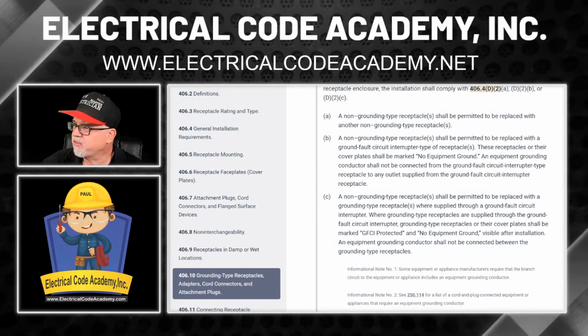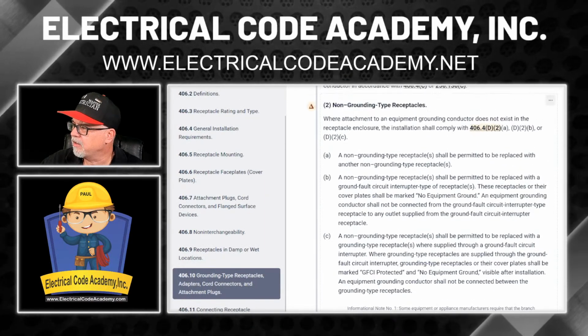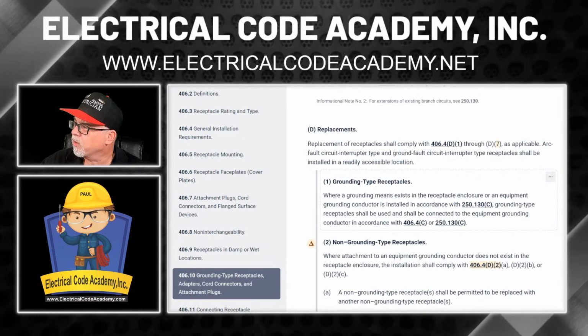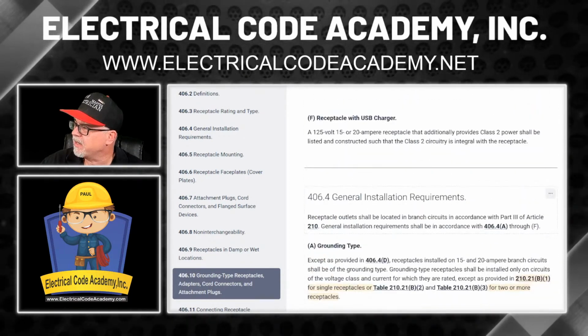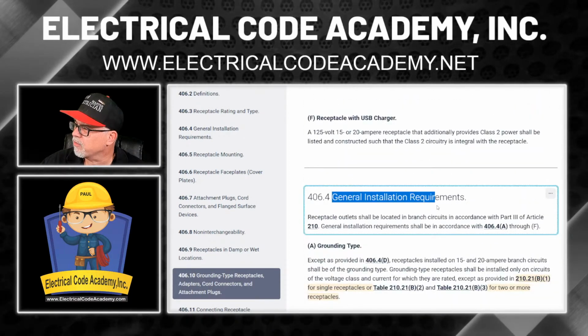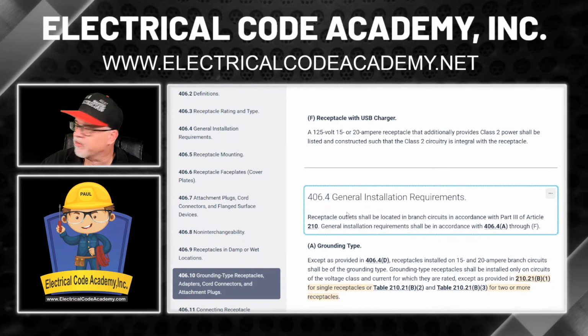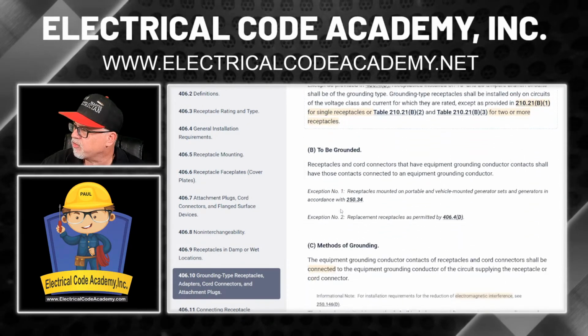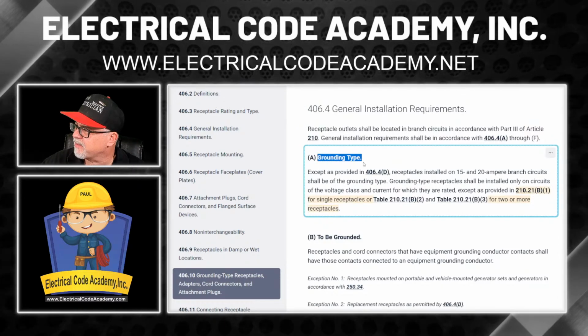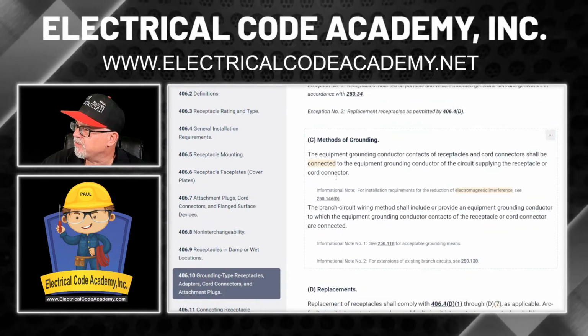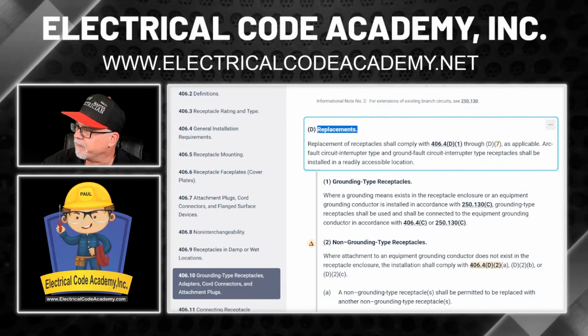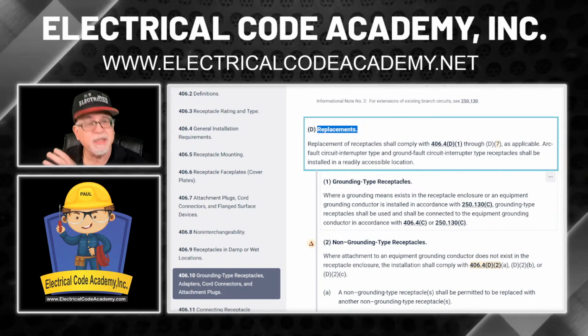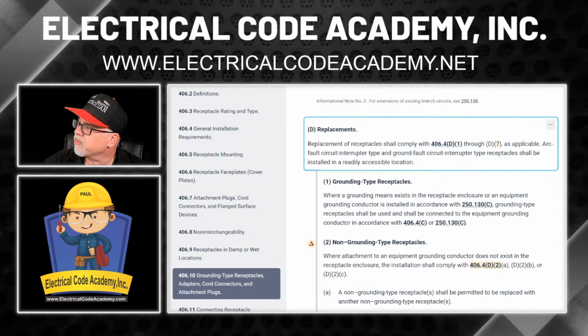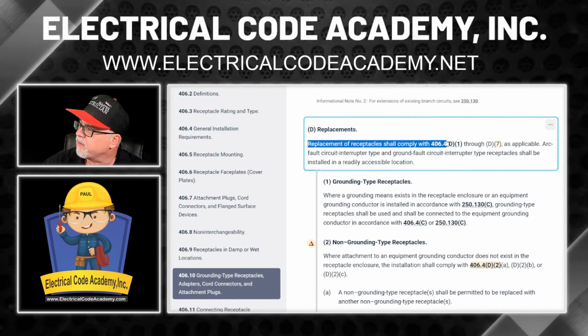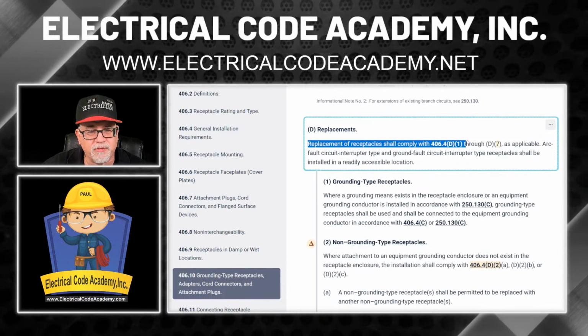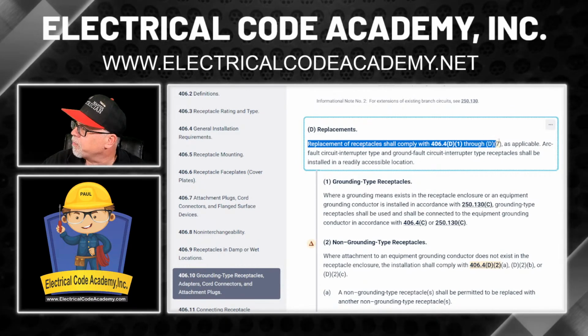So I'm at the NEC. I'm using Link. Link is a product from NFPA. And we're at the replacements. So here at the beginning of this is general installation requirements 406.4 for receptacles, okay? And so again, obviously they have to be the grounded type, and it goes on and says, well, what about if you're doing a replacement? So if we're doing a replacement like what he's doing, it says replacement receptacles shall comply with 406.4 D1 through D7, so different options here, as applicable.